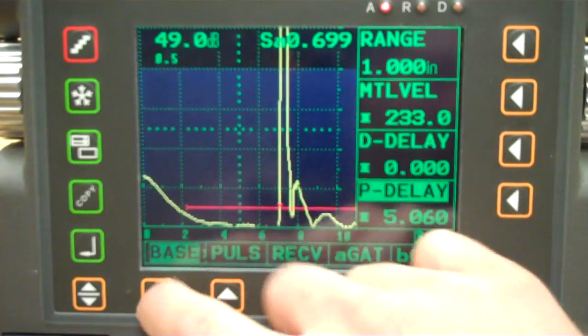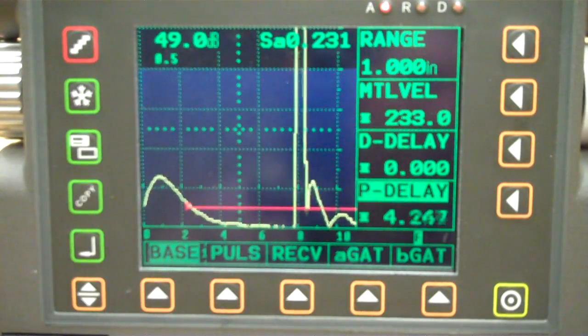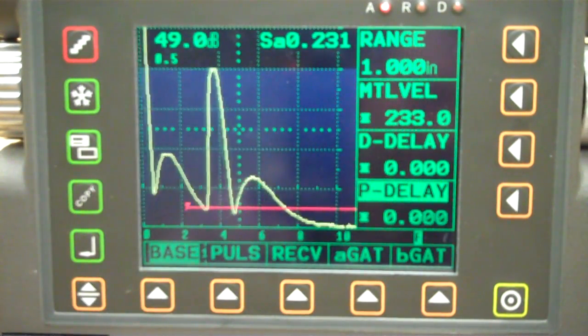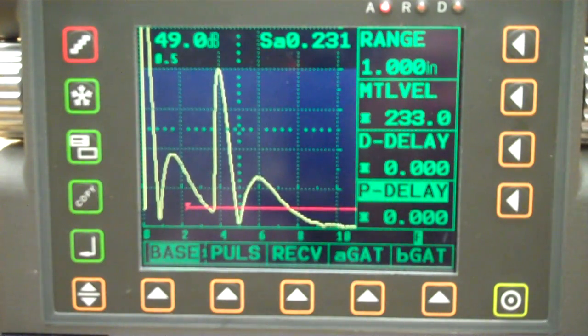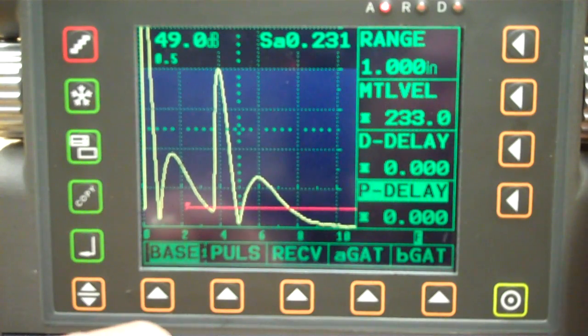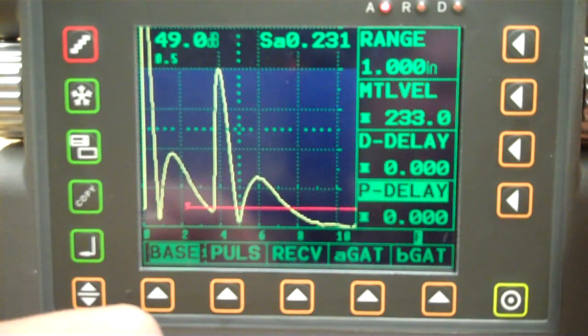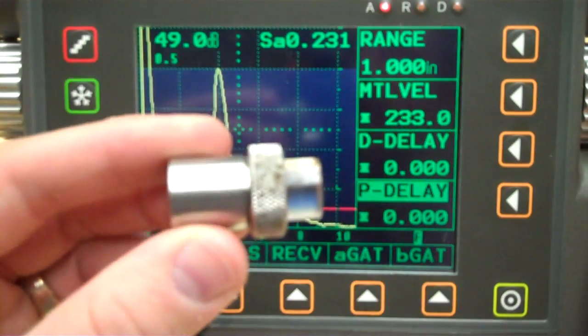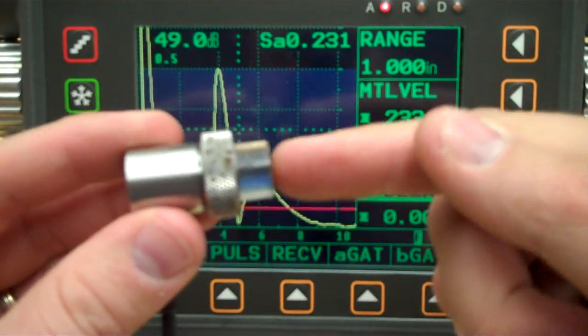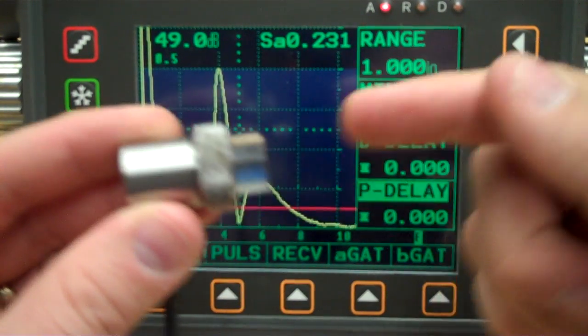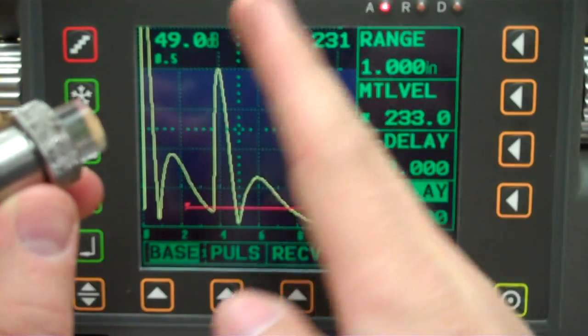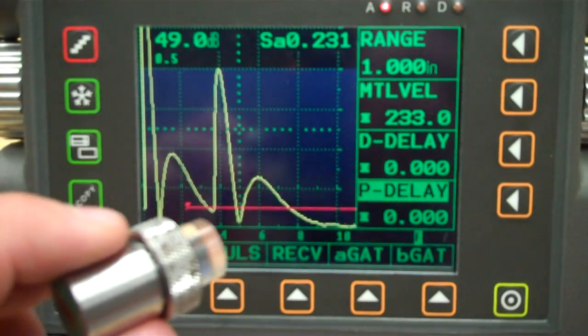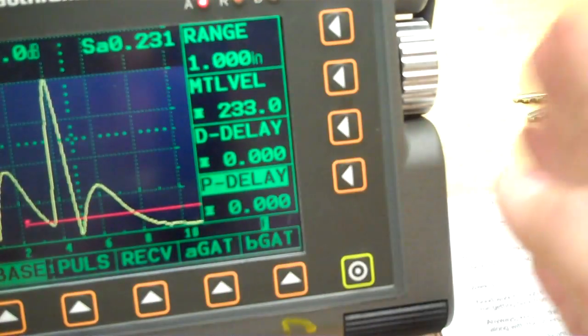Let's take our base menu, take our probe delay all the way back to 0. Okay, still on steel, still 1 inch range. If we go here on our 1 inch signal, our 1 inch step block, we got nothing. That's because our delay is slowing that sound down right here. Since that's slowing that sound down, that means that 1 inch signal is actually going to be out here somewhere. So we need to find it.